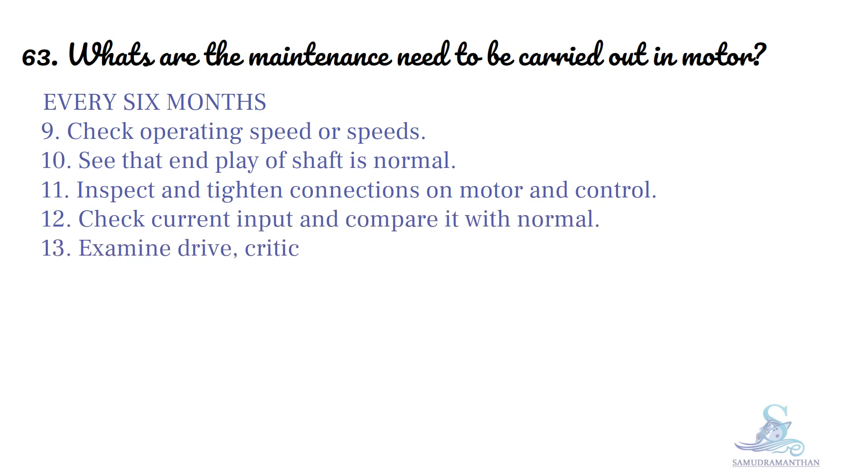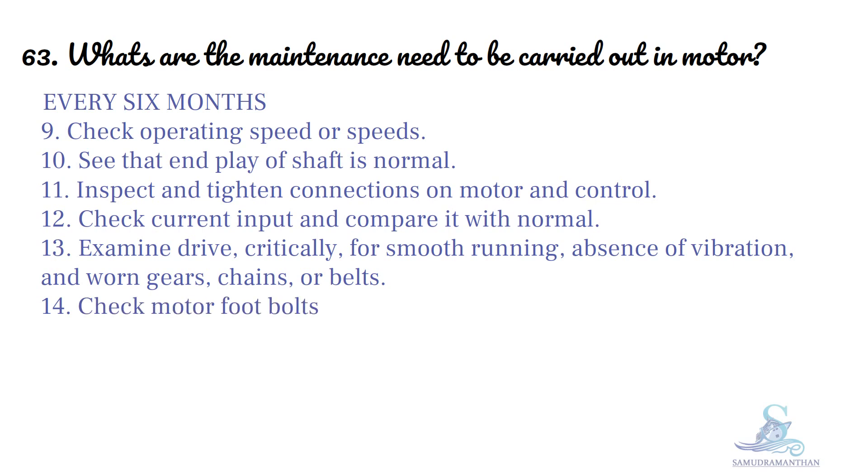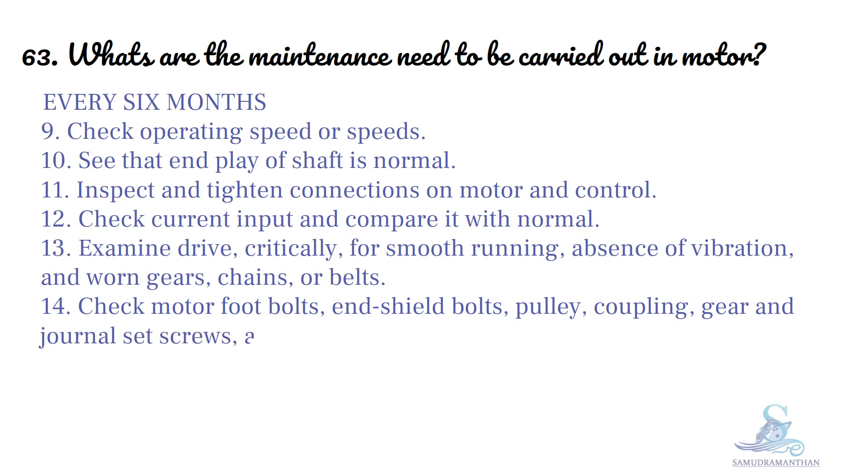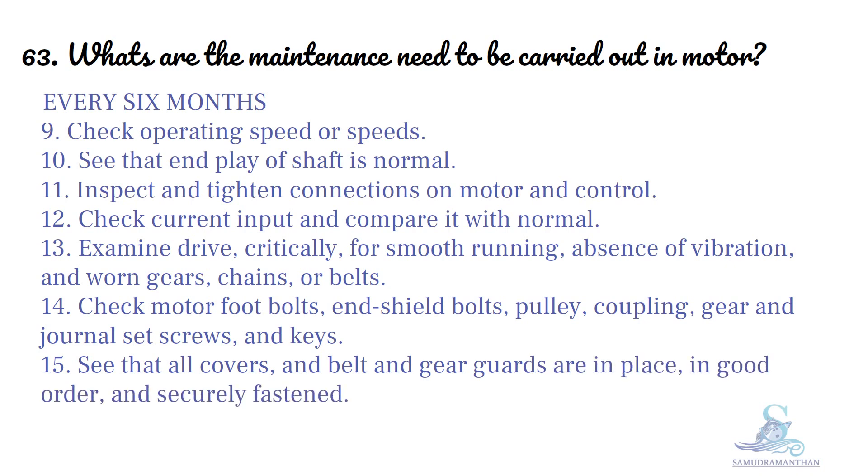Examine drive critically for smooth running. Absence of vibration and worn gears, chains or belts. Check motor foot bolts, end shield bolts, pulley, coupling, gear and journal set screws and keys. See that all covers, belts and gear guards are in place in good order and securely fastened.